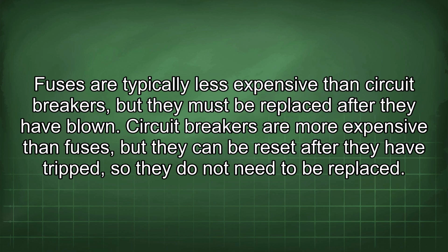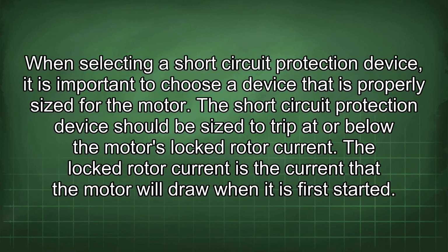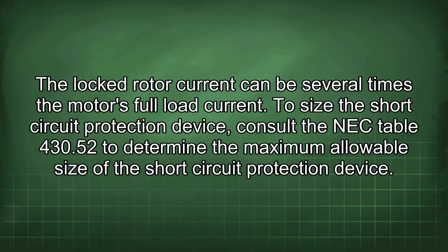Fuses are typically less expensive than circuit breakers, but they must be replaced after they have blown. Circuit breakers are more expensive than fuses, but they can be reset after they have tripped, so they do not need to be replaced. When selecting a short circuit protection device, it is important to choose a device that is properly sized for the motor. The short circuit protection device should be sized to trip at or below the motor's locked rotor current. The locked rotor current is the current that the motor will draw when it is first started. The locked rotor current can be several times the motor's full load current.